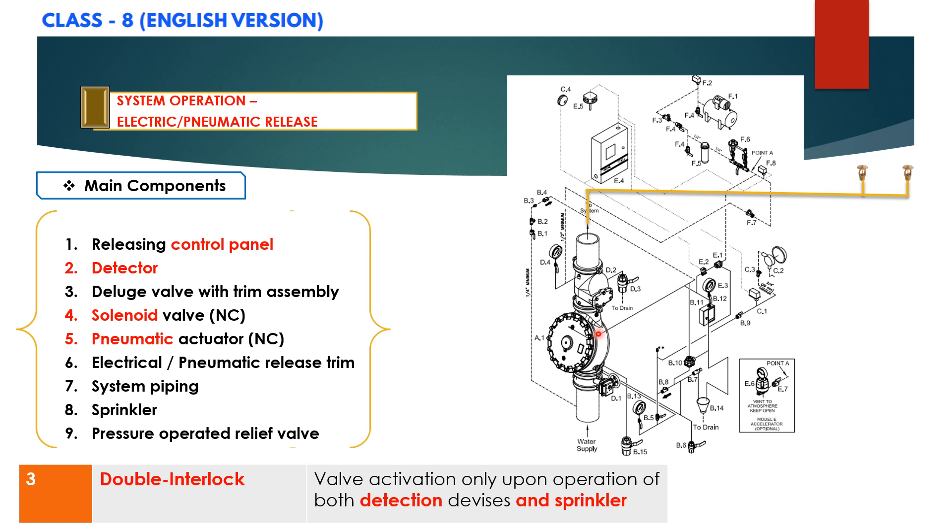this line is connected on the deluge valve priming chamber. In the set condition, water supply pressure is trapped in the priming chamber by check valve B4 and both electric actuator, which is normally closed E2, and normally closed pneumatic actuator.